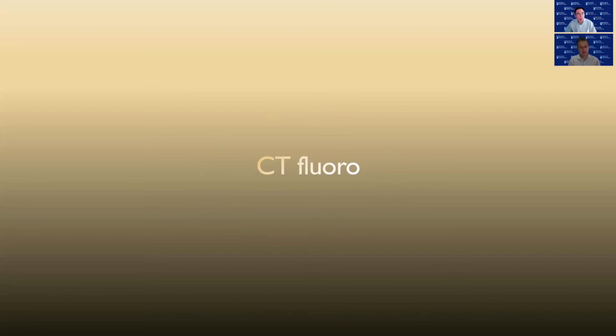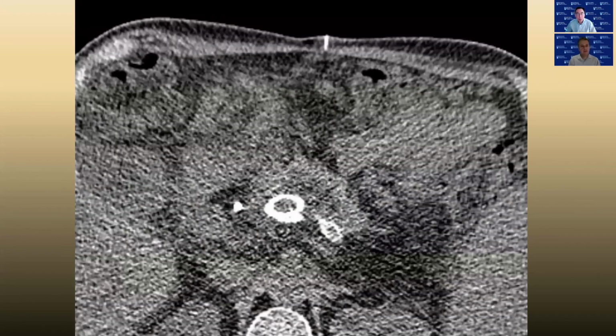So we usually default to about 30 mAs for our CT fluoro acquisitions. And you can step back when you take fluoro images, which is very, very helpful. You can even put a lead drape over the patient's body below the field to decrease scatter. And then, most CT scanners have software that does these partial rotations on the opposite side of the patient. So that helps also minimize scatter to the operator. But anyway, what I love about CT fluoro is it allows me to very quickly do complicated procedures.